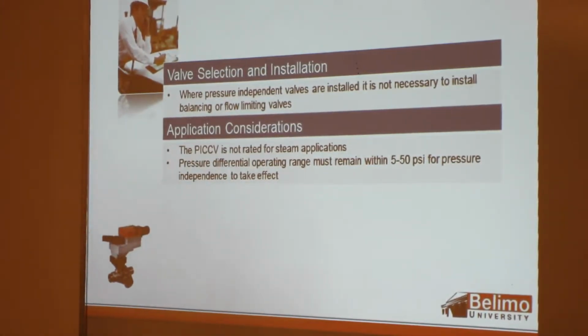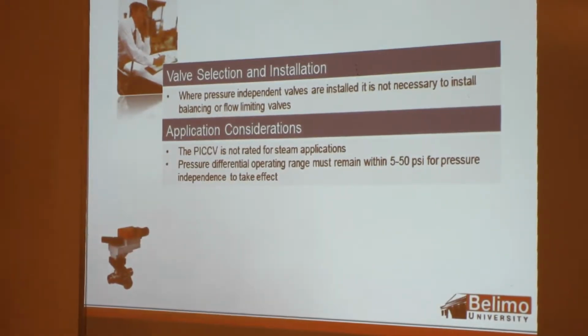So, as far as selection and installation, not necessary and not recommended to install any kind of balancing or flow limiting devices. A couple reasons for that. Well, first of all, of course, this valve does that for you. Second thing is, in order to maintain your efficiency, or peak efficiency anyway, if you put in a balancing valve or flow limiting valve, that's just adding, or I should say taking away from the pressure drop that could be going to the pressure independent valve. And you want to make sure you have enough drop across that valve. You don't want to have to increase your pumps to get more of a drop because you have those additional valves in place. As I mentioned earlier, PICCV is not rated for steam applications, and you need to be in the 5 to 50 psi drop across the valve.